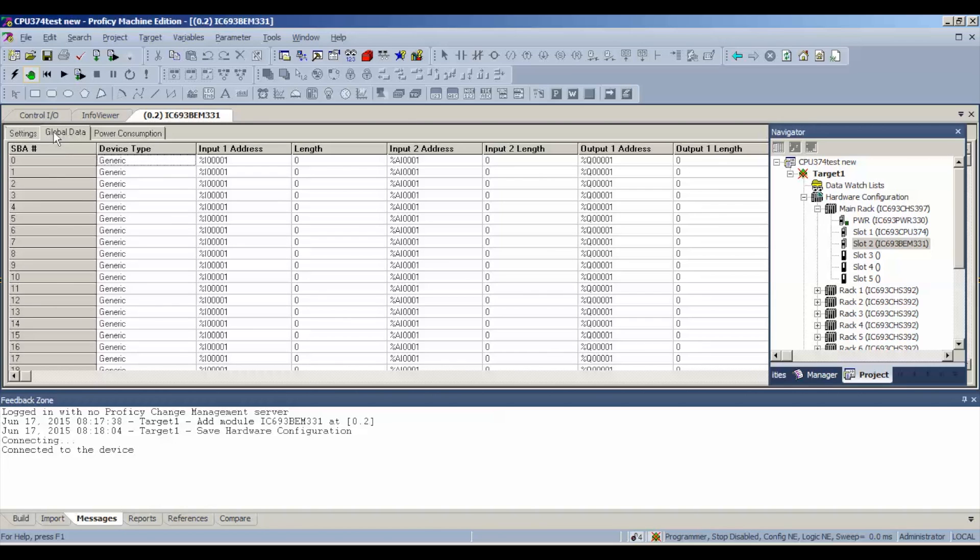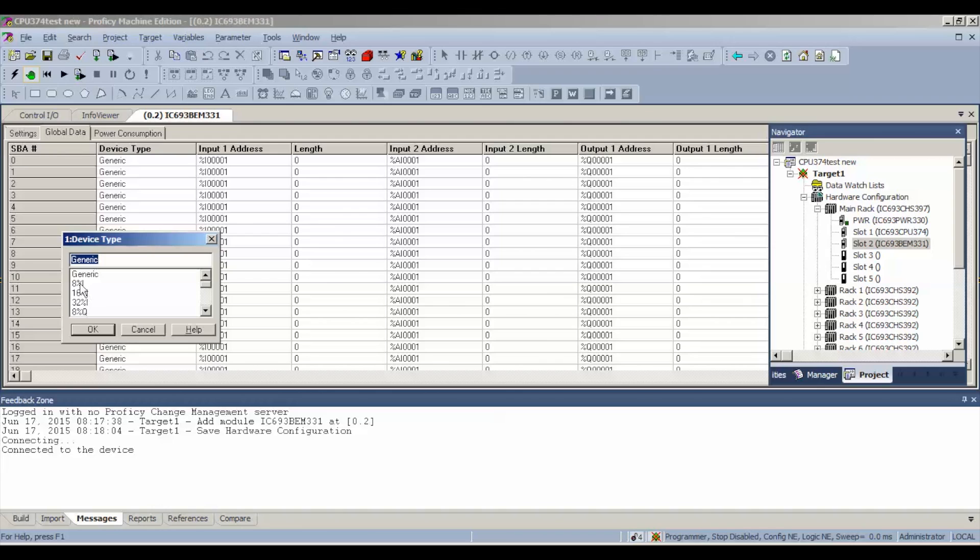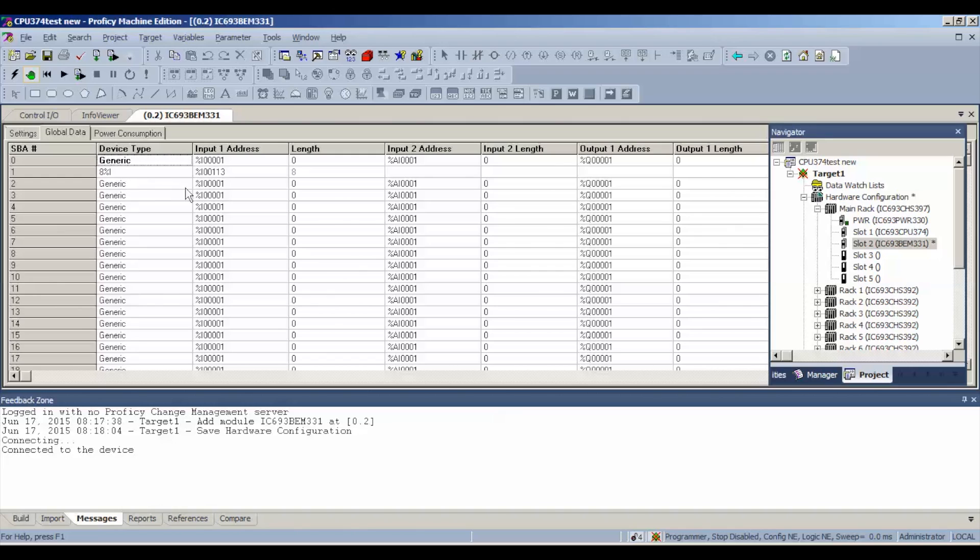As I mentioned before, our bus address number for this block is number one. You can double click on where it says generic where I've got my arrow or you can right click and hit data entry tool. It's eight discrete inputs, so eight percent I. It'll automatically establish an input starting address, which in my particular case is 113. Yours might be 0001. Just check to make sure you know where your address is so you can look at where the inputs are going to be coming in.